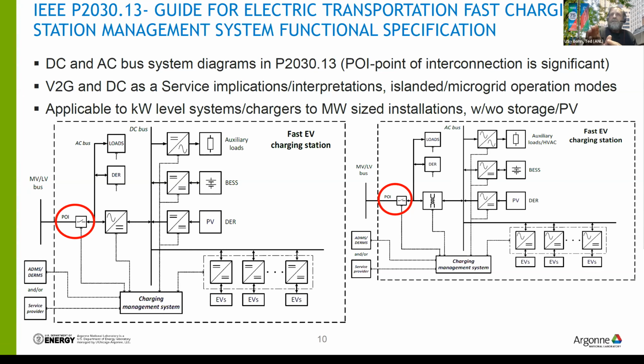On the right is an AC coupled system. MVLV is the medium voltage, low voltage bus. The red circle is a point of interconnection, where the utility ends and the facility starts. In the lower center is the charge management system, where vehicle grid integration and other smarts go on. The dotted lines are the nodes this system can see or communicate with. To the right of the charge management system are the AC to DC charge stations shown earlier, and the EVs are the end load.